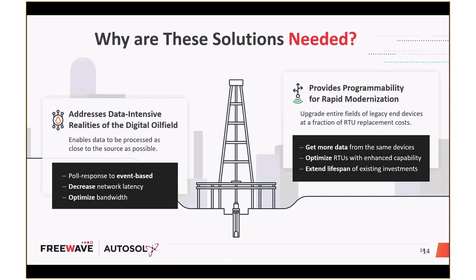As we move forward in the oil field, the theory is more data, faster. The poll-response method of current SCADA systems is already being tested as people want to monitor more things and bring in more data points — it's inefficient when only 3 out of 50 data points actually changed. Processing data close to the source means we don't need such a robust enterprise-deployed system. It also allows upgrading entire fields of legacy devices: instead of replacing RTUs, the ZumLink or ZumIQ edge-enabled radio can bring the edge to older devices, collecting all their data and publishing only what you need.